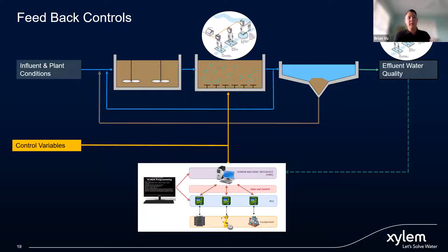A little more advanced than your DO control. You get a little more aeration energy savings from that, because you're treating what's actually coming out the back end. If your ammonia increases, you need to increase your blower speed. If it decreases, you decrease your blower speed. So this is feed forward feedback control, which is a little more advanced than the feedback controls.